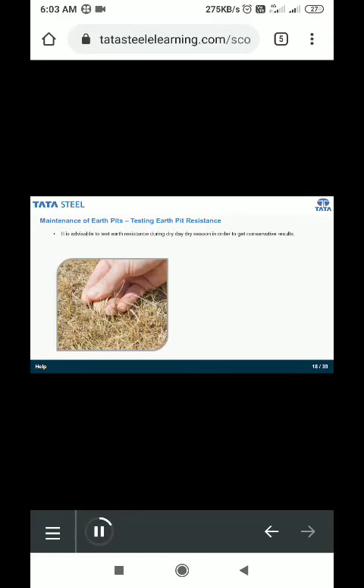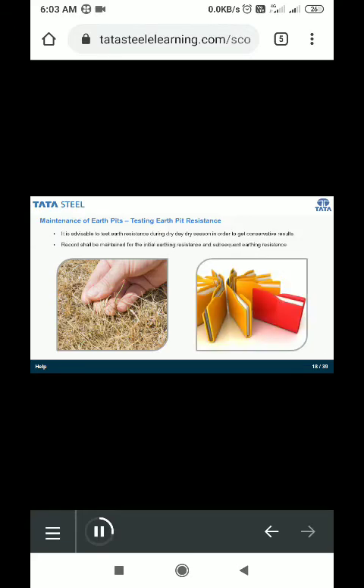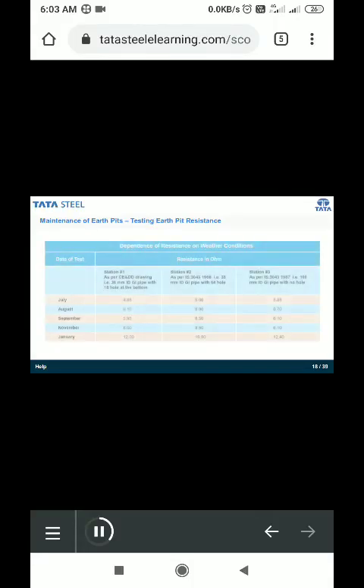The next step is to test the resistance of the earthing pit. It is advisable to test earth resistance on a dry day, in the dry season, in order to get conservative results. Further, records shall be maintained for the initial earthing resistance and subsequent earthing resistance. In this context, it is important to have a look at this table.